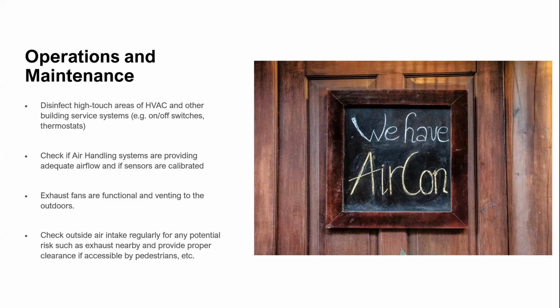Check the outside air intake regularly for potential risks such as exhausts nearby, and provide proper clearance if accessible by pedestrians and other pollution-generating sources. There is a minimum intake distance of about 3 meters, but BERDE, the green building system for the Philippines, actually recommends 10 meters from the outside air intake to any exhaust. This is linked to bullet number 3, because some buildings have their exhaust right beside the fresh air intake, which is bad, because whatever you're exhausting may also be taken in by the fresh air fans.